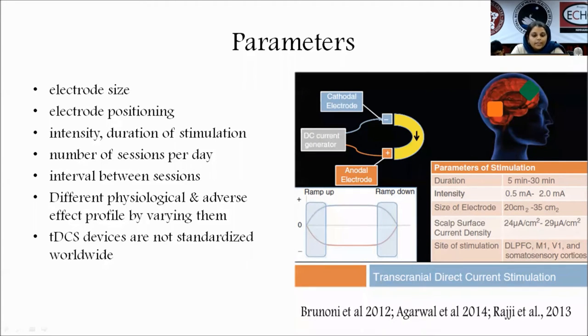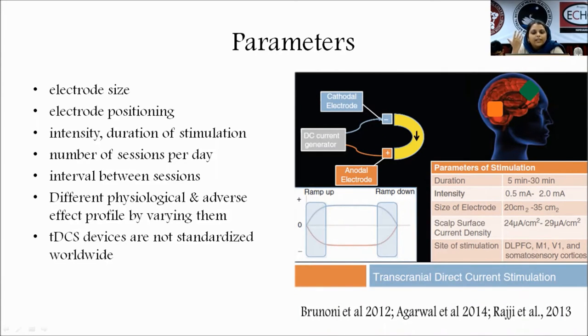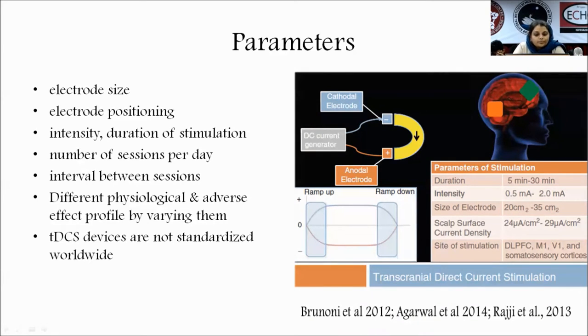The ramp-up and ramp-down phases are also important. During the ramp-up phase there is a gradual increase in intensity of stimulation. If there is a sudden increase in intensity, the patient will experience discomfort and side effects. Around 30 seconds of time is given for gradual increase and gradual decrease — that is ramp up and ramp down.